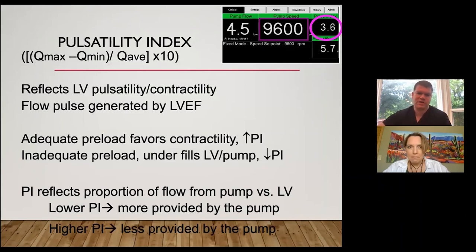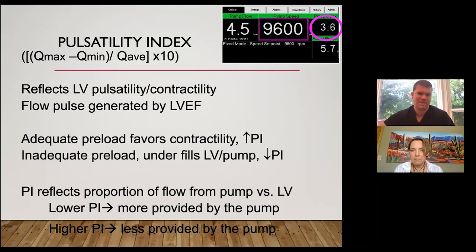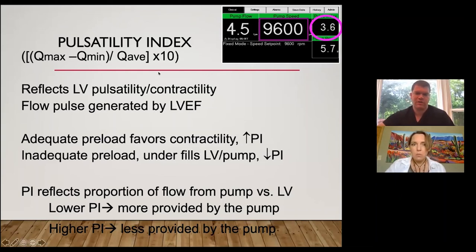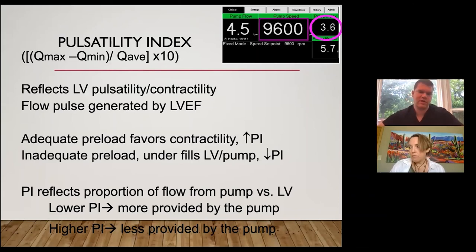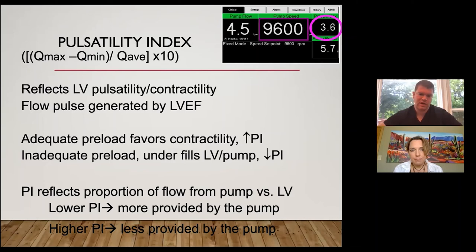The pulsatility index formula involves the difference in flow — Q maximum minus Q minimum — over the average flow, reflecting how much flow changes over the cardiac cycle. It reflects LV pulsatility and contractility. Adequate preload favors contractility per the Starling curve and increases PI; inadequate preload underfills the LV and pump, lowering PI. A low PI means more of the cardiac output comes from the pump; a higher PI means less is provided by the pump.